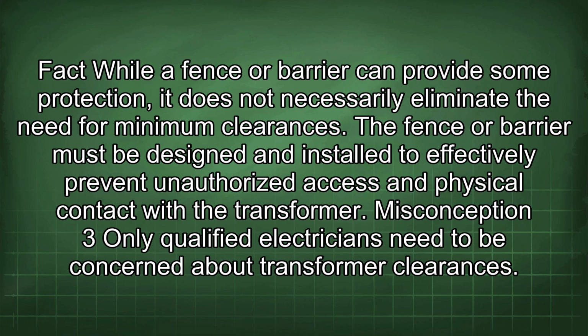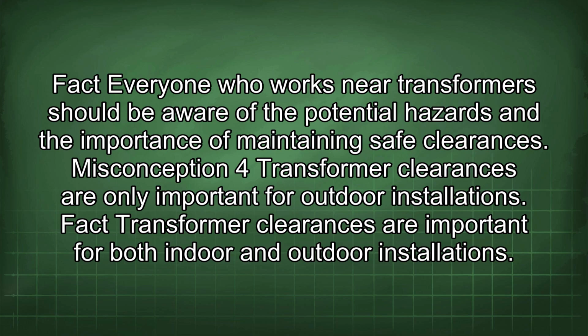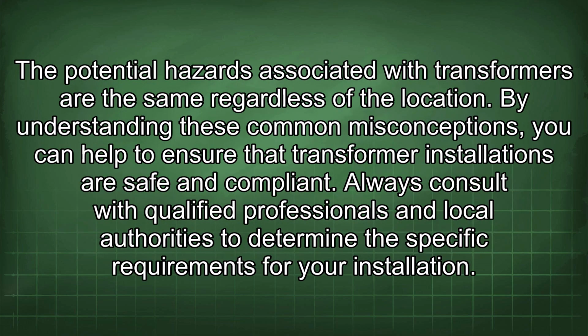for minimum clearances. The fence or barrier must be designed and installed to effectively prevent unauthorized access and physical contact with the transformer. Misconception 3: only qualified electricians need to be concerned about transformer clearances. Fact: everyone who works near transformers should be aware of the potential hazards and the importance of maintaining safe clearances. Misconception 4: transformer clearances are only important for outdoor installations. Fact: transformer clearances are important for both indoor and outdoor installations. The potential hazards associated with transformers are the same regardless of the location.